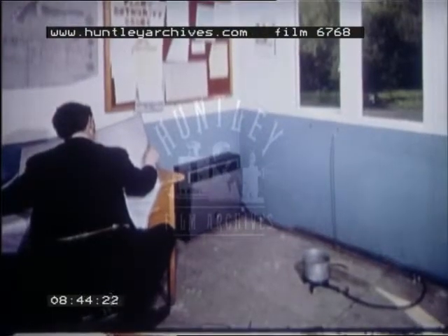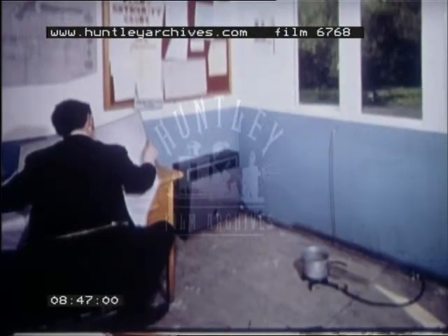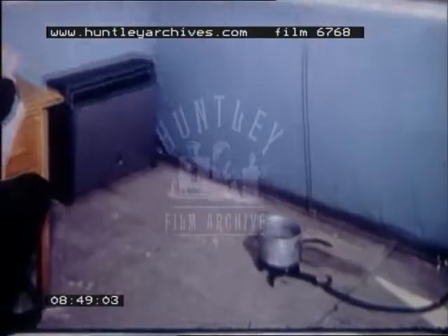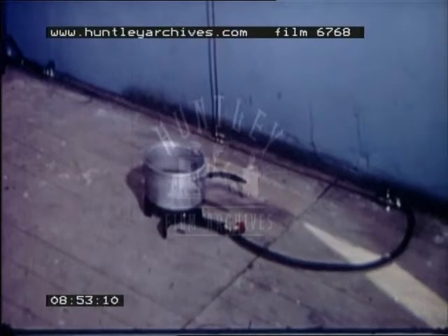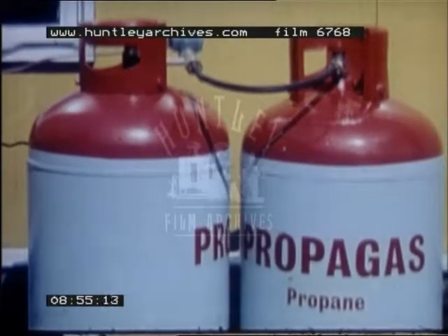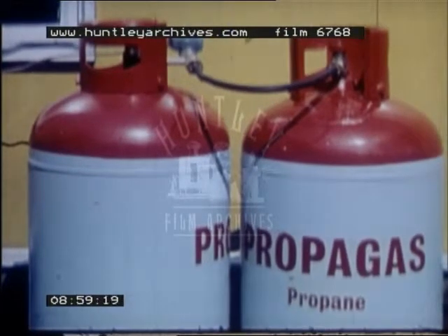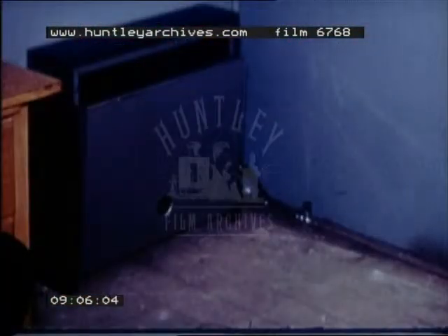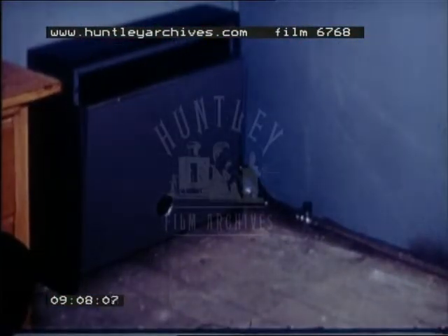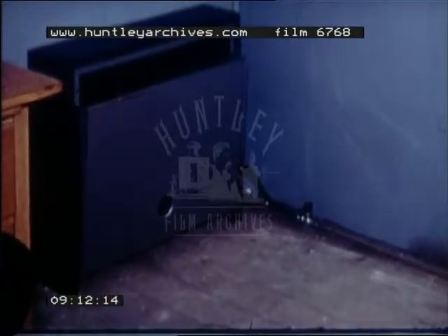The heating of site huts, especially during winter, is important on any building site. Radiant heaters, and also small boiling rings, are commonly fired on propane gas. However, it is essential that the cylinders are kept outside the hut. If you do have a leak at the connection to the cylinder, it's far better outside and away from any naked lights. By having the cylinders outside, it is obviously necessary to have a further gas tap inside next to the appliance. Or is it?